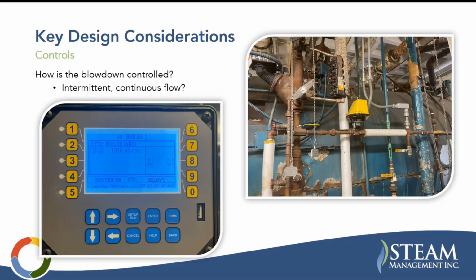Here's another example of a good, typical surface blowdown control system that you would see. This is your conductivity probe. You see these often, they look just like this, sitting down in the surface blowdown water. And then you have this controller here modulating an actuated ball valve just like this. And they often look exactly like this, but across different manufacturers may have a different color actuator. The ball valves are usually this type of ball valve, and this is a pretty typical looking setup.